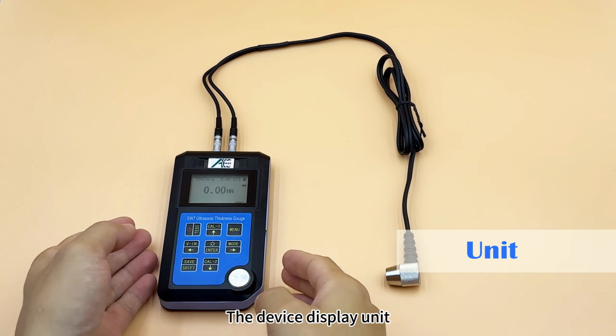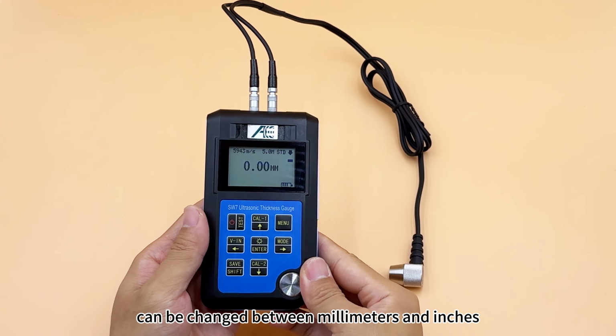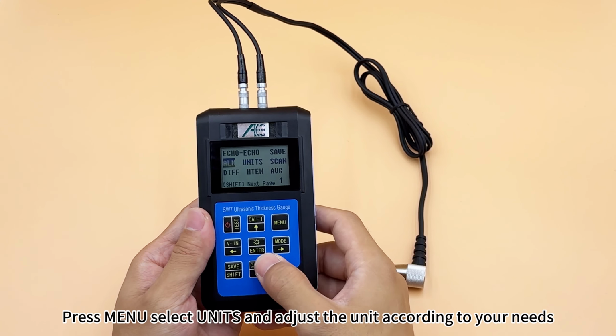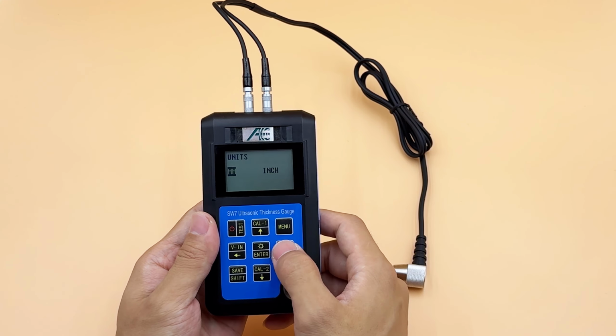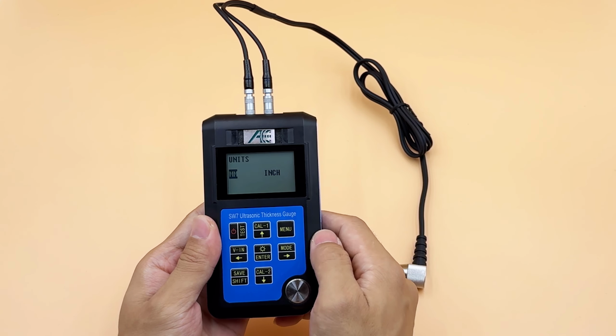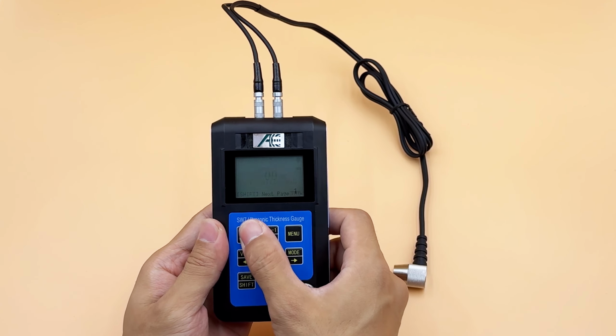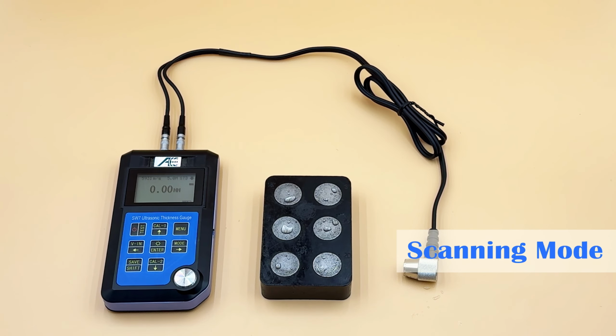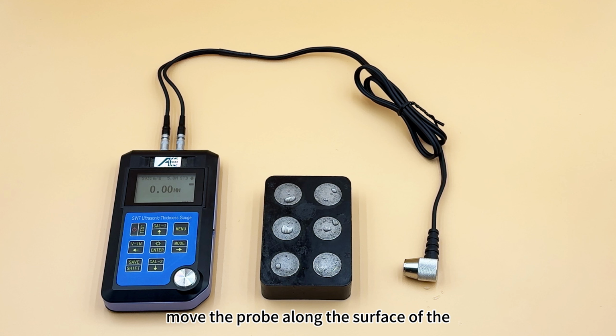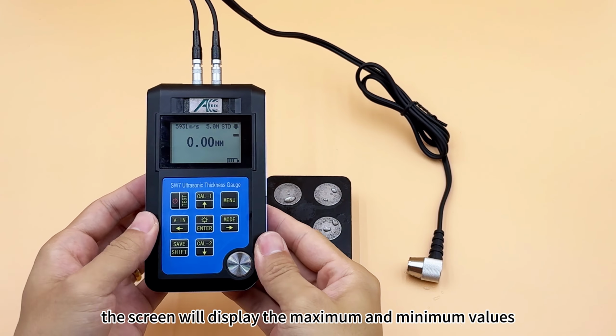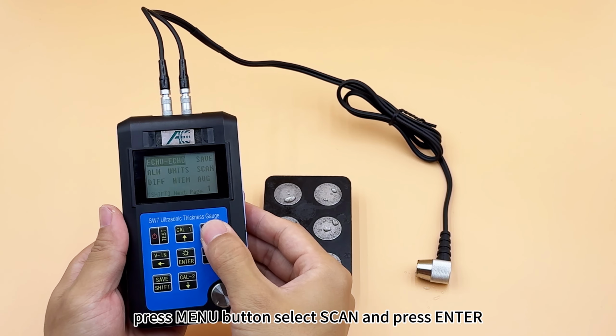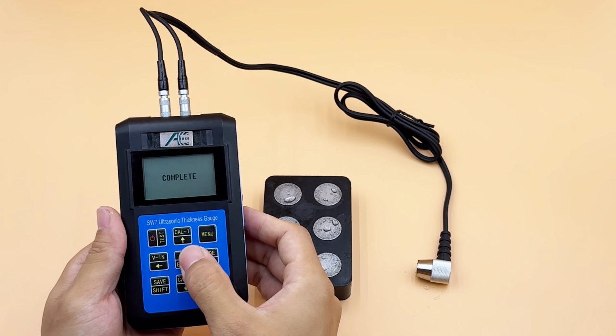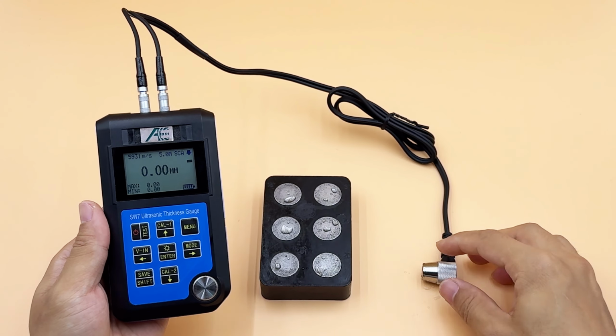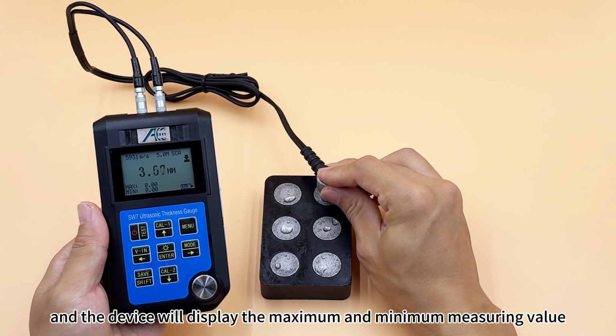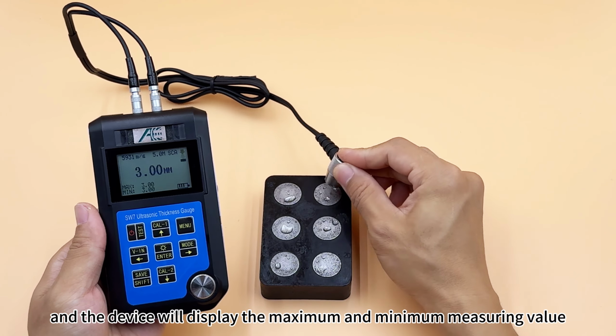Unit. The device display unit can be changed between millimeters and inches. Press Menu, select Units, and adjust the unit according to your needs. Scanning mode. When the coupling is well maintained, move the probe along the surface of the object being tested. The screen will display the maximum and minimum values during the scanning process. Press Menu button, select Scan, and press Enter. Measure several test blocks of varying thickness, and the device will display the maximum and minimum measuring value.